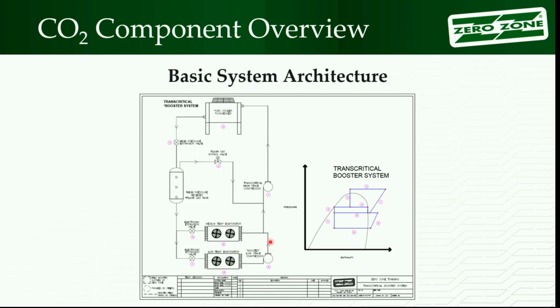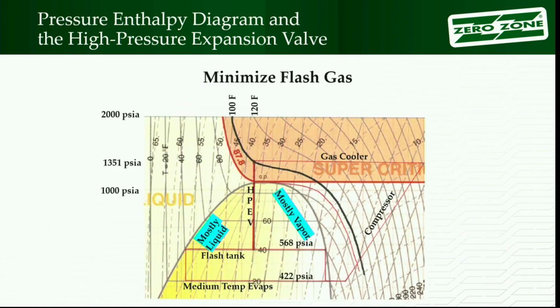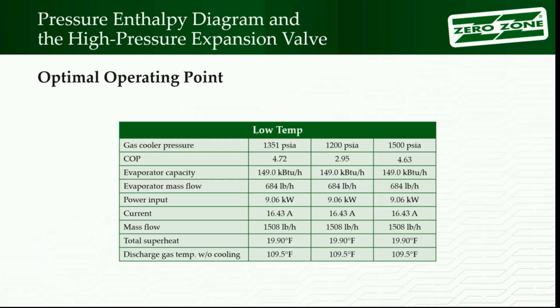Besides, the booster is going to be hot, so we're not used to seeing that. So some things you have to be aware of when you work on it. So that's kind of the story with it. That's why the valve does what it does. It's trying to mitigate that flash gas. And the higher the pressure, the more liquid you get. The lower the pressure, the more flash gas you're going to get with that.